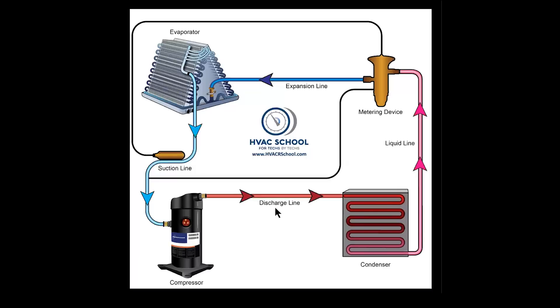The most common restrictions out there are liquid line dryers — either inside or outside the condensing unit, by the air handler or by the condenser in typical residential applications — or metering devices: inlet screens on metering devices that have clogged up and aren't allowing enough refrigerant through, or maybe a bulb that's lost its charge so the power head isn't opening the valve properly. Those are the common causes of restrictions, along with occasionally a kinked liquid line.